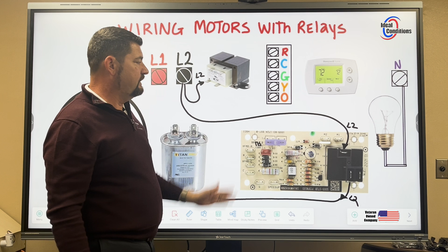But if you run one leg at a time, then you can verify each end where the supply of voltage is coming from and where it's landing, and it's harder to mess that up. And it doesn't take any longer. You're going to get done within the same amount of time. Now I'm going to come over here. Now my transformer on the high voltage side is complete.